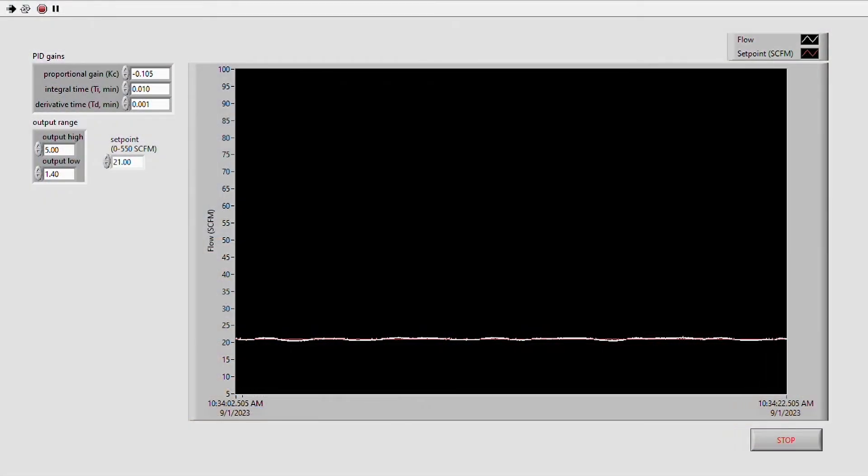This is the LabVIEW VI we are using to control and observe our gas flow control setup. The red line on the graph is our flow set point, and SCFM in the white line is the measured flow as reported by our flow meter. You can see that the flow is stable around our set point of 21 SCFM with a bit of noise that's acceptable given the full range of the flow meter.